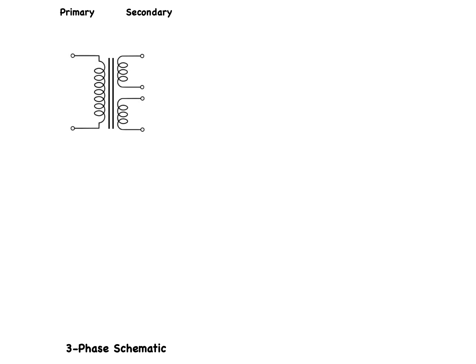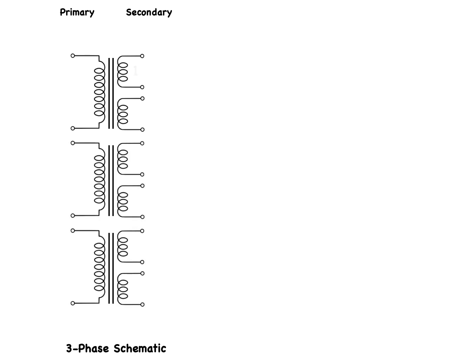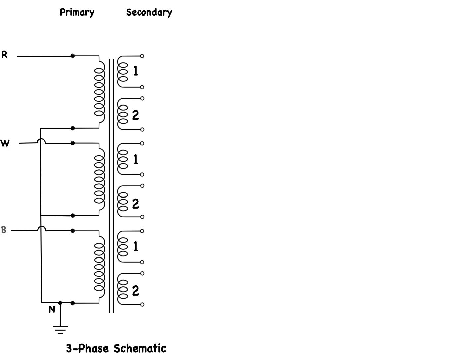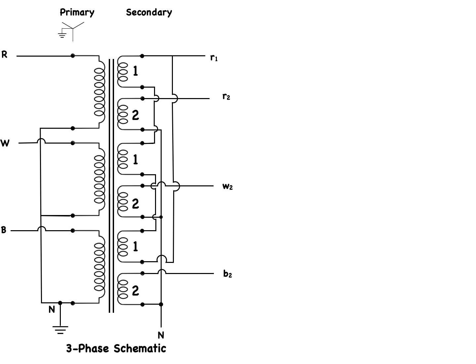Now let's look at a transformer with a dual secondary — one primary winding magnetically linked to two secondary windings. Because we are dealing with a three-phase system, we need to consider three of these transformers, which could be wound on the same core or be three individual transformers forming a transformer bank. To keep track of connections, let's number the secondary windings of each transformer 1 and 2. Let's connect the primary windings in a grounded Y configuration, connected to a balanced three-phase system — red, white, and blue. Let's connect the number 2 winding of each transformer secondary in a Y configuration — ungrounded — calling the connections r2, w2, and b2. Next we connect the number 1 winding of each transformer secondary in a delta configuration, calling the connections r1, w1, and b1.